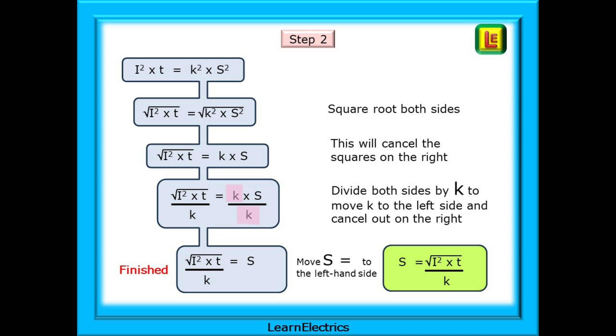Now move on to step 2: square root both sides. This will cancel the squares on the right-hand side, leaving the left-hand side as it is. Then divide both sides by K — this moves K to the left side and we can cancel the Ks on the right. There we have the finished formula with S on its own. Tidying up, S equals the square root of I squared times T, divided by K, as shown in the book.